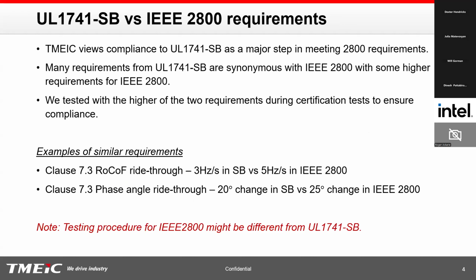And often, when we put these standards on the same level, certain numbers are slightly different. So when we do our certification test, we try to meet the higher requirement compared to either SB or 2800. Some samples are shown here. For example, rate of change of frequency ride-through in clause 7.3 requires about 5 hertz per second of ride-through in IEEE 2800, whereas in 1741 SB we have about 3 hertz per second requirement. So we tested for the 5 hertz per second requirement, and for phase change ride-through we tested for 25 degrees as required by 2800 instead of 20 degrees.